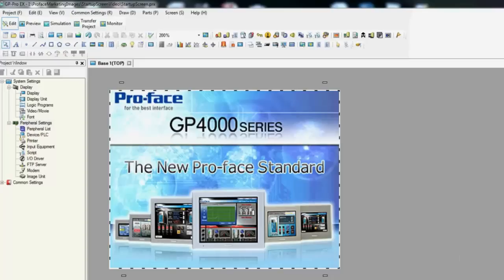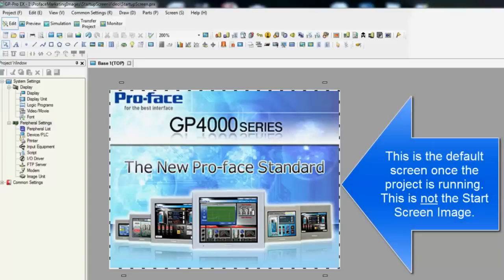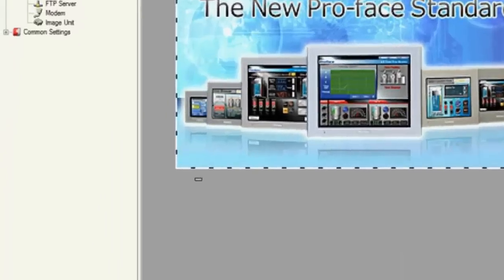For best results, the screen graphics should be sized in pixels to match the resolution of the HMI. Here we have a GP4301T project open. This is a 320x240 pixel screen size. Therefore, the startup image should be sized to this pixel dimension.